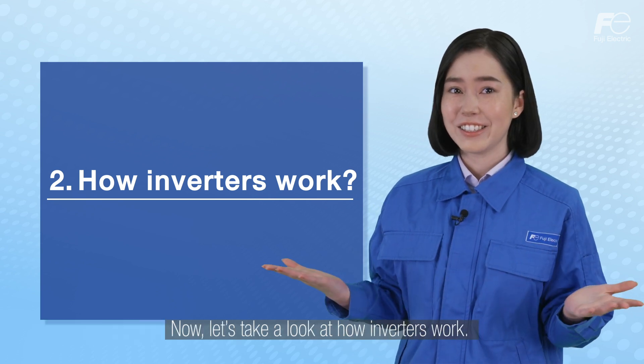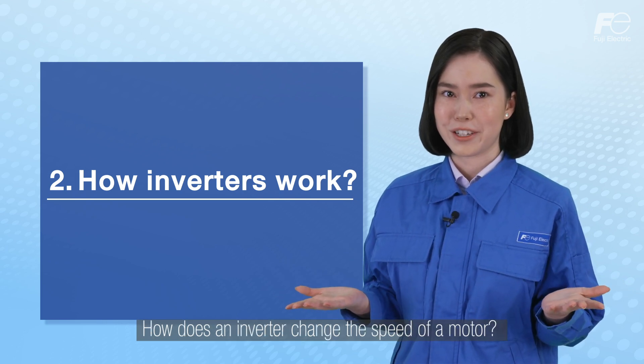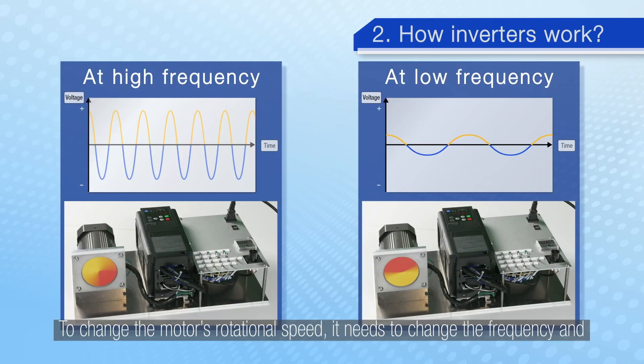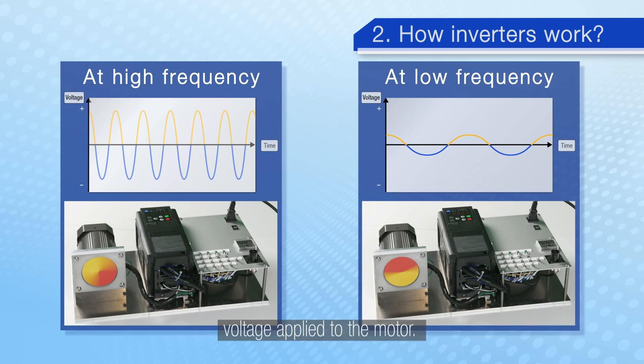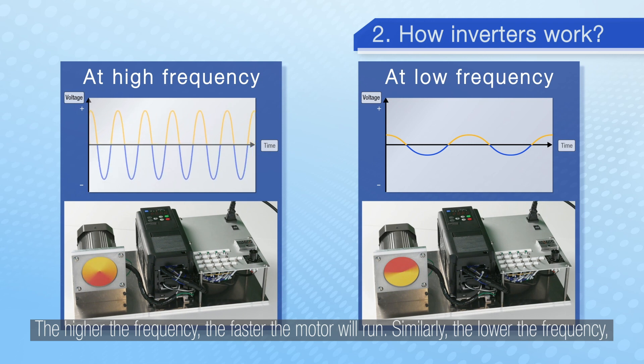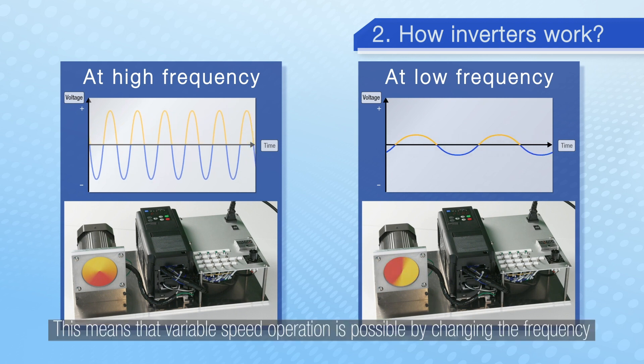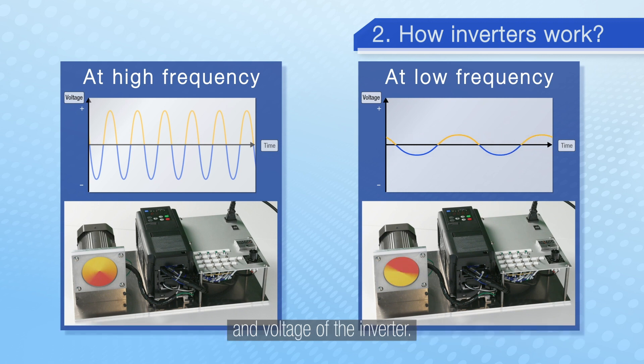Now let's take a look at how inverters work. How does an inverter change the speed of a motor? To change the motor's rotational speed it needs to change the frequency and voltage applied to the motor. The higher the frequency the faster the motor will run, and similarly the lower the frequency the slower the motor will run. This means that variable speed operation is possible by changing the frequency and voltage of the inverter.